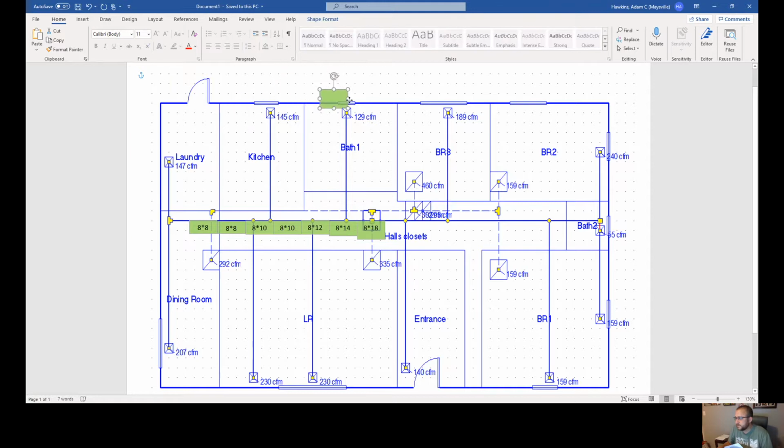So we got to say, okay, how much is left? Well, we had 800 to start with. We took off 550. I think our math's not going to come out right. I think we need to make our first piece bigger. I think when we did our stuff, it did come up to about 1100. So it's possible that you might need a little more than 400 CFM per ton. If your house is built really well, you might have to upsize your blower or speed your blower up to move enough air, because the house is built well. There's not a lot of heat load, but you still have to be able to move the air. So this first piece, we may have to upsize that.